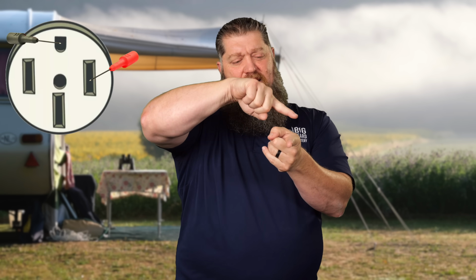How to verify that? Go up and connect to the ground now. So you still have the one connected to one of the hots. By the way, both sides are your hots. Okay? You go between the hot side and the ground, 120 volts. Let's do this hot side and ground, 120 volts. But in either case, when you come down between the hot and the neutral and you see 0 volts, you have verified you have an open neutral.